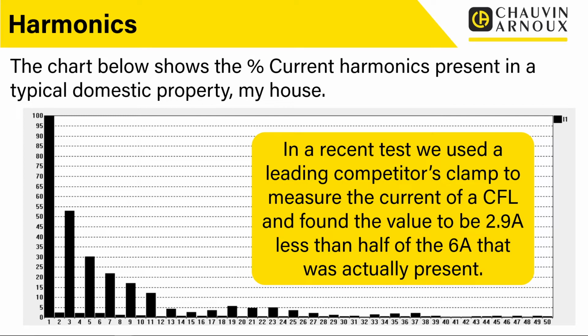But we recently did a test using a leading competitor's clamp meter to measure the current of a CFL, a compact fluorescent luminaire. And we actually found that the value measured on the clamp was 2.9 amps. But that was actually less than half what was actually present. What was actually present was 6 amps. So when you take into account the actual current in all of the harmonics, we've got 6 amps there.